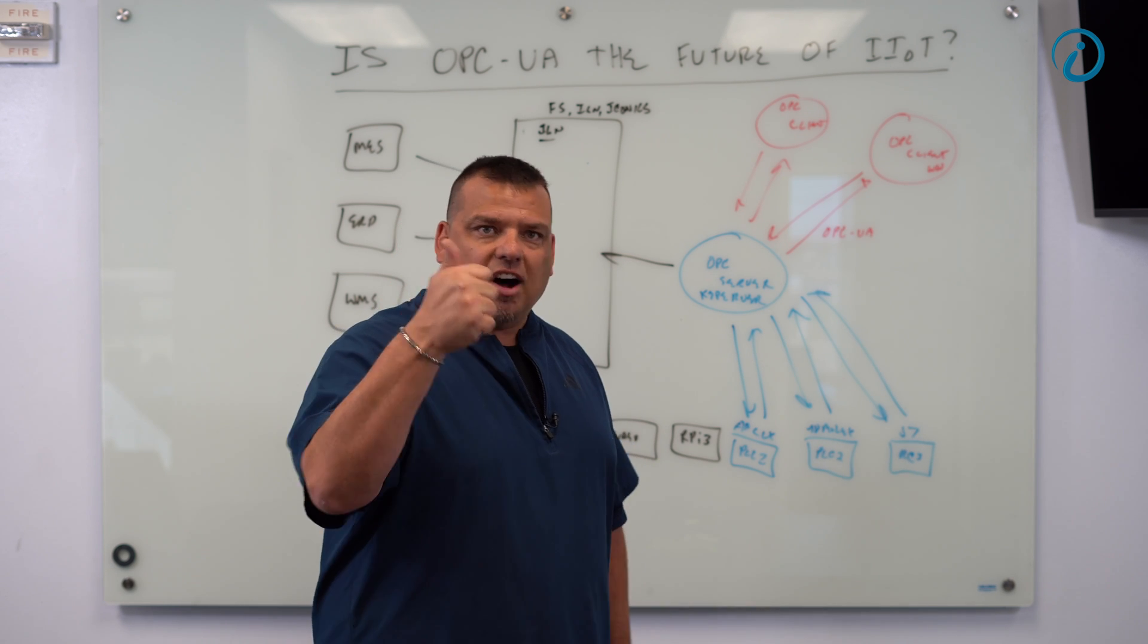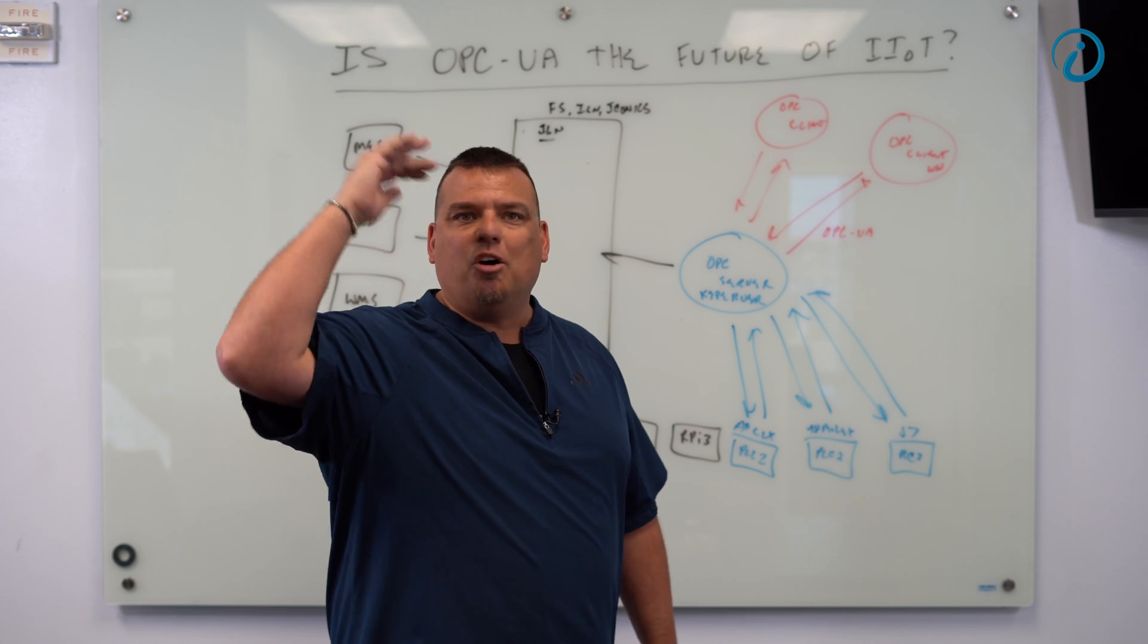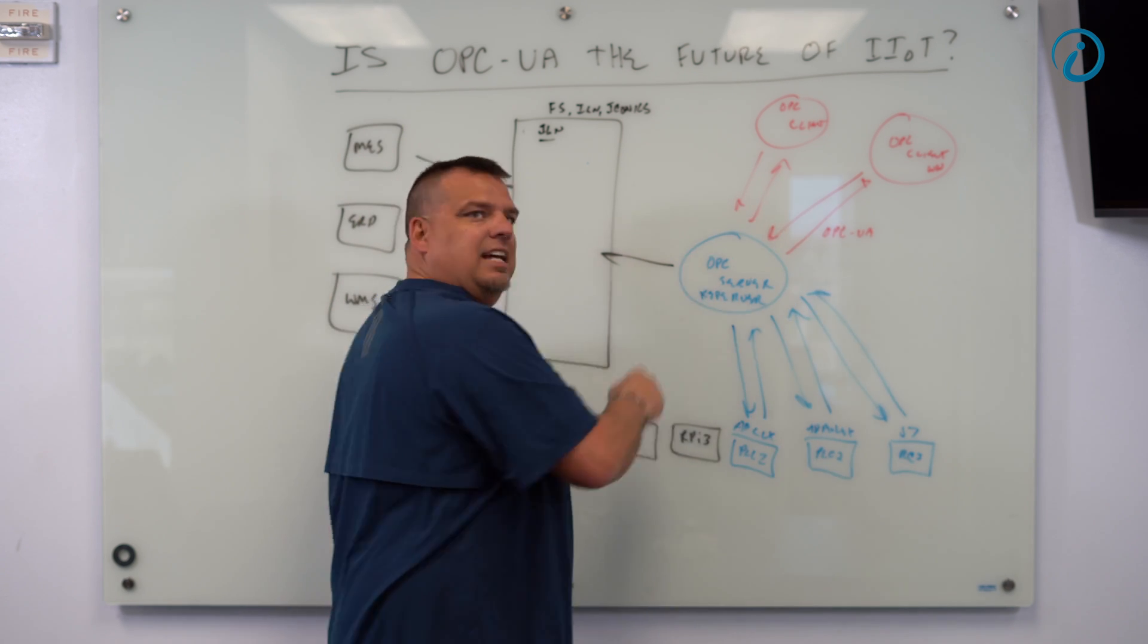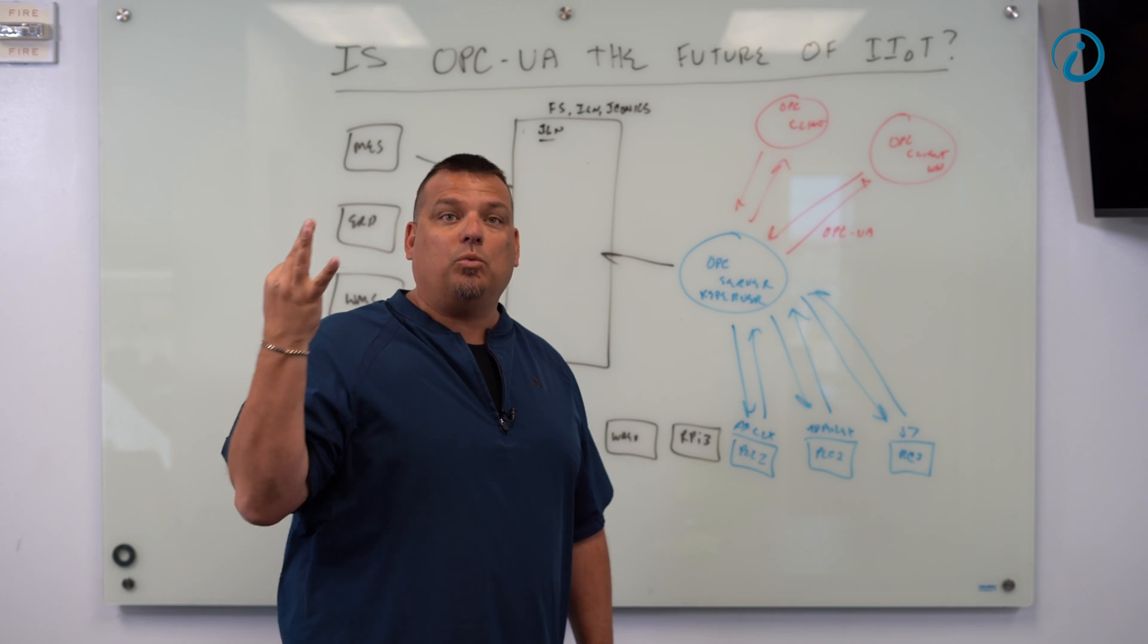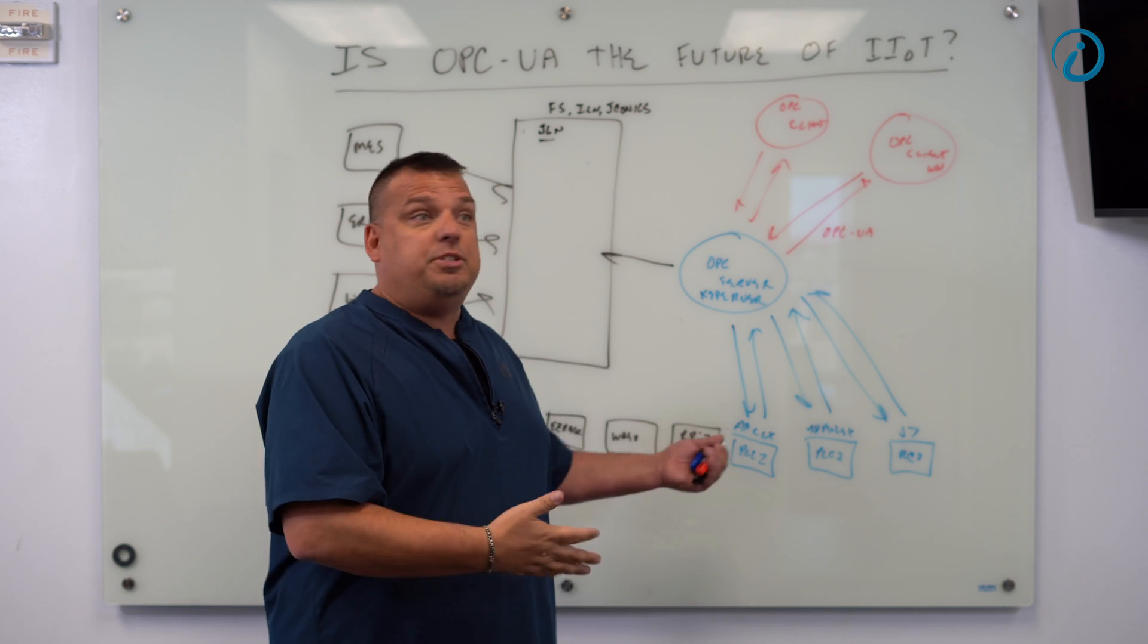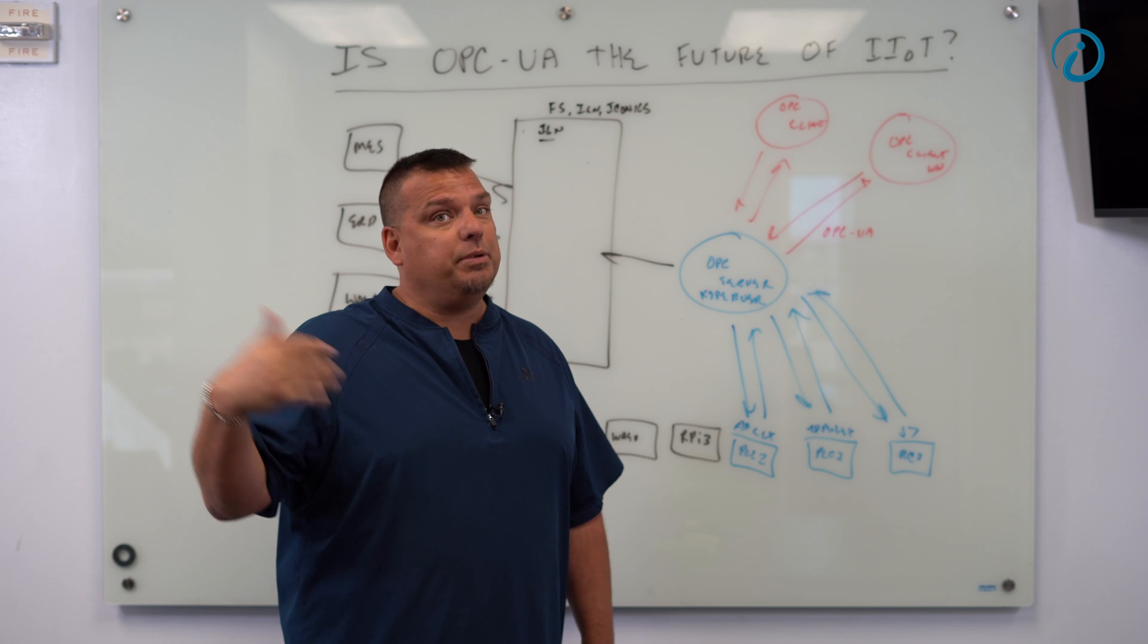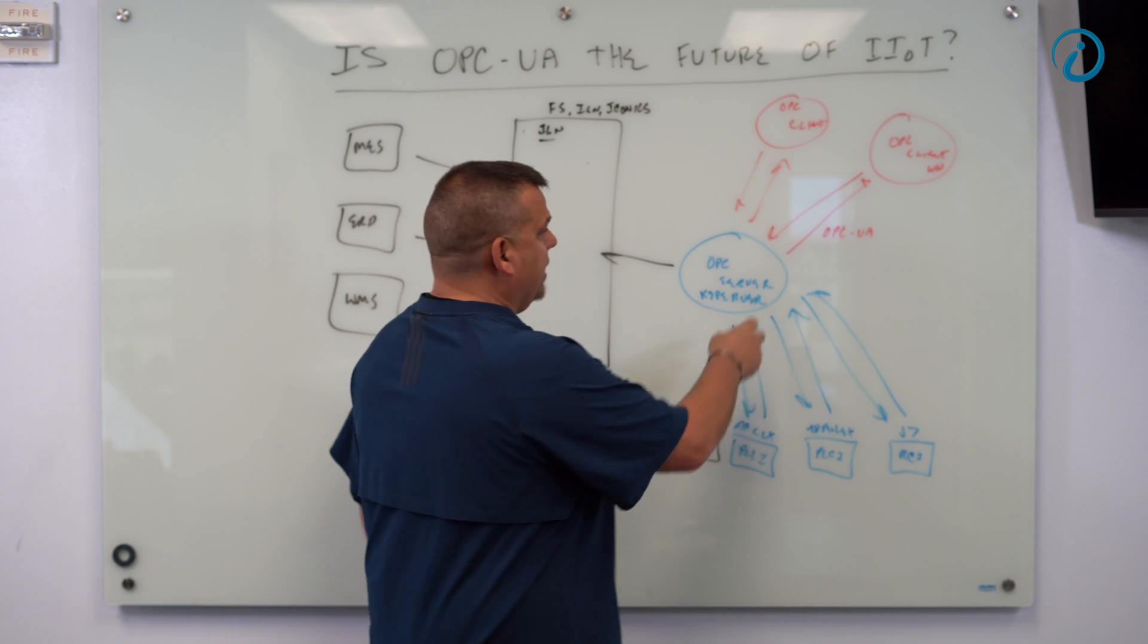Do you know why it is that more PLCs don't have OPC servers built into them? Yeah, it's the cost of developing it in each unit, but also it's the overhead. OPC UA is incredibly resource intensive. And remember what our third requirement is, it has to be lightweight. Now OPC UA is stateful. It is not open. You gotta be part of the club. It isn't report by exception. It's poll response. The server does all the work.